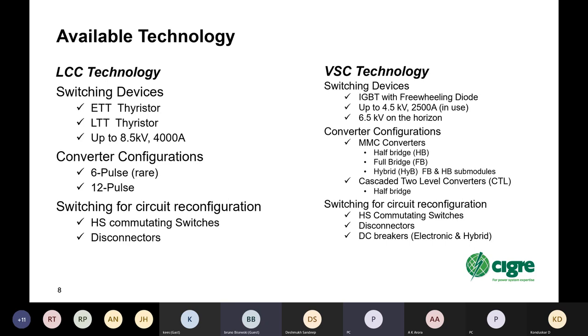There's also an older configuration that was used immediately at the start of the VSC technology that was cascaded two-level converters. The technology is, I understand, no longer being offered, and it was similar to the half-bridge technology in the MMC. So switching for circuit reconfiguration is again similar to LCC. You can use high-speed commutating switches for areas where you don't need to interrupt fault current, where you can commutate the current, disconnectors for switching when there's no current, and DC breakers, both electronic and hybrid, electronic and mechanical, which can be used to actually interrupt DC current.